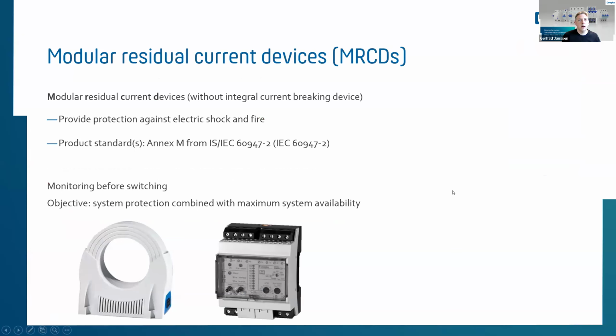The last device group, let's say, are monitoring devices. One of the newest products, I would say, on the market. So with those products, you are able to monitor residual currents. And if you would like, you can also shut the system, or let's trip it with a different device. But the main purpose is to monitor residual currents, again, to provide protection against electric shock and fire, but monitor before switching. So if you do not want to switch because the machinery is not able to switch down because the whole production process might end up in a mess, you are able to see residual currents arising in a system, being able to have predictive maintenance, send somebody out before the RCCB or the device has to trip because of risk situations. So monitoring devices as well available.